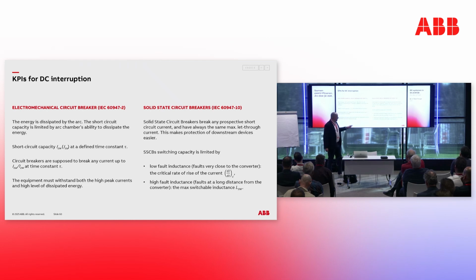So the main thing to watch out for when using a solid-state circuit breaker, when I simplify, of course, is to check what's the lowest fault inductance that can occur, but also what's the maximum. This is usually not as critical, but it could happen that you have a very large drive or something giving you a lot of inductance. Then the energy stored in the circuit can be a little bit too much for the energy absorbing circuit and can destroy it.